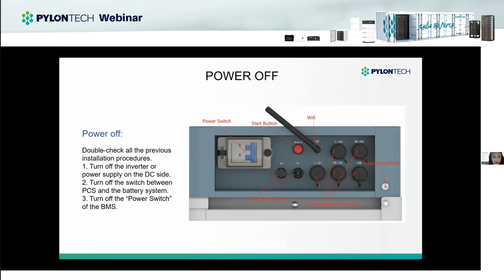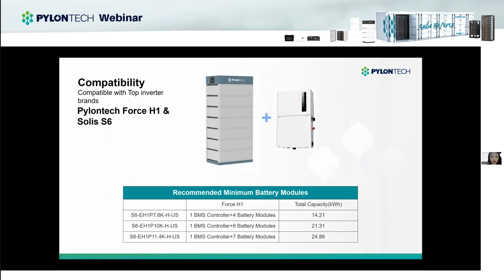ForceH is compatible with many inverters in the market. In the US market, we always use Solis, Sol-Ark, Kehua, and here we use the Solis as an example. Here is the recommended minimum number of battery modules and the inverter module. The choice depends on the power and the battery series. Our ForceH is 0.5C. So for example, the 7.6 inverter could configure 1 BMS and 4 battery modules.